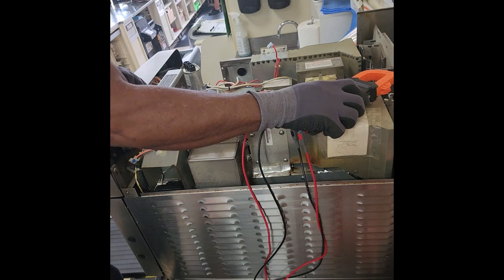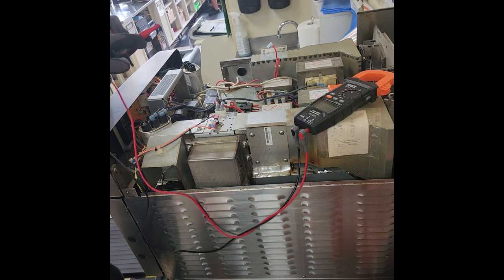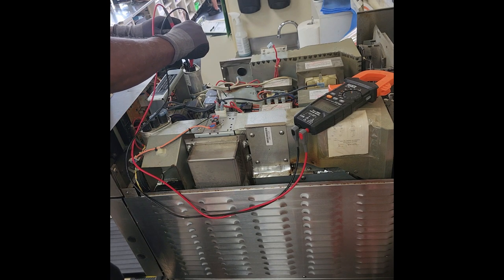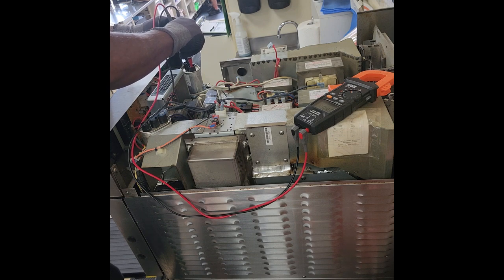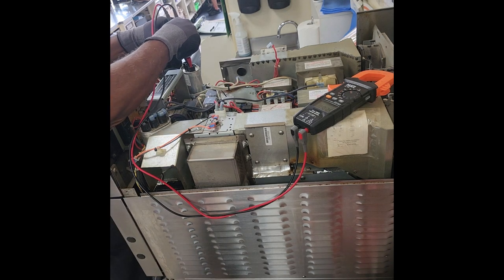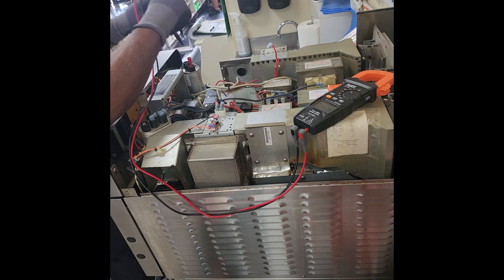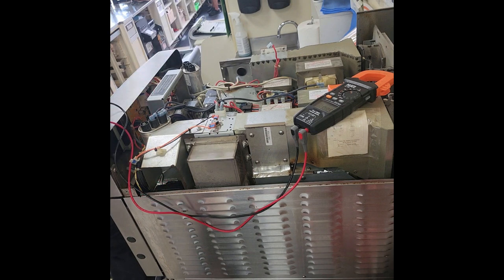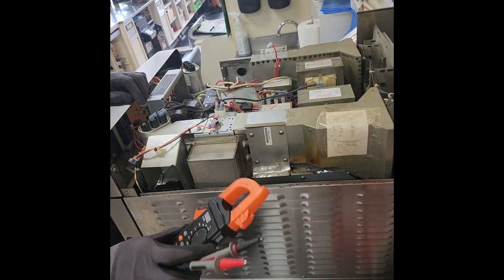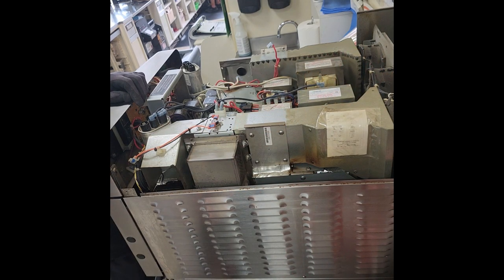So right now I'm going to check the capacitor, see what we got. Okay, I got 0.93, and the range on this is 0.91. I believe this has a plus or minus 10%, so it's within range. That capacitor is within range, I got 0.93 microfarads.